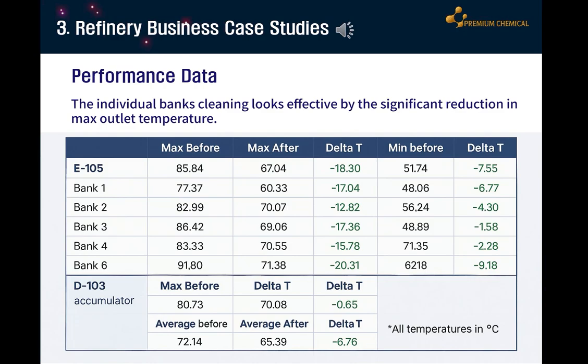Now, let's examine the performance data for the external chemical cleaning of the air fin cooler. The E105 air fin cooler had accumulated contaminants on its fin surface due to long-term operation, reducing heat transfer efficiency. Therefore, external cleaning was performed, and the performance improvement was analyzed based on temperature data before and after cleaning.